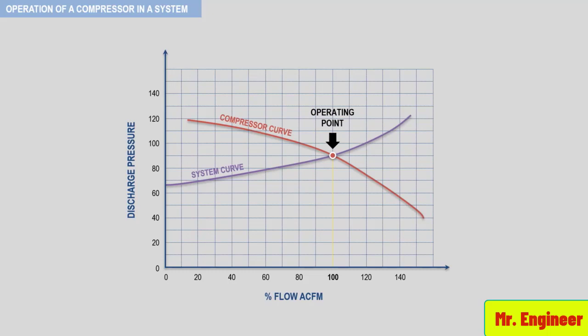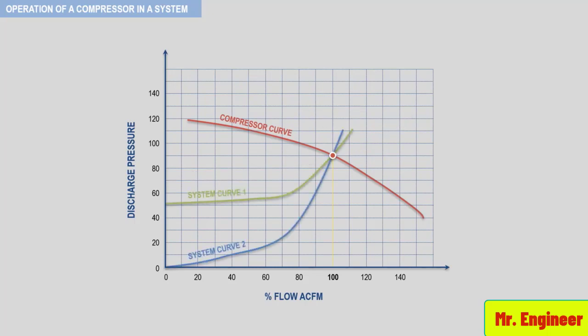This point of intersection is also known as the operating point, which will be covered in detail in the next video. In the next figure, two different system resistance curves representing two different process systems are shown. The curve starting at zero differential pressure represents a process system where only system resistance is present — when the compressor is shut down, the pressure in the system is zero. This would typically describe a recycle process. The second curve starts at 50 psi differential pressure, showing that a pressure differential of 50 psi exists when the compressor is shut down. You can see that the higher the percent of vessel pressure in the process system, the flatter the system resistance curve is.